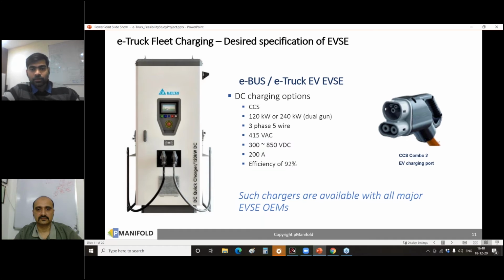That's the case of a 240 kilowatt charger, and the maximum current carrying capacity, the peak current, would be about 200 amperes. An important aspect is the conversion losses due to AC to DC conversion. OEM claimed efficiency lies between 92 and 95%, so losses of 5 to 8% could be expected around these chargers, which needs to be factored in while sizing infrastructure.